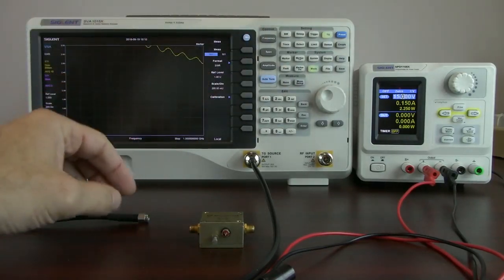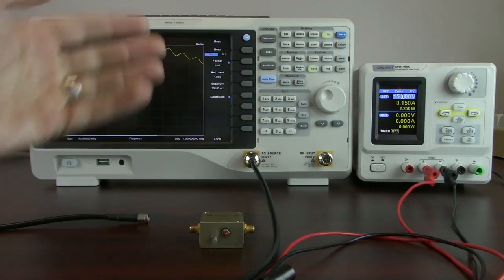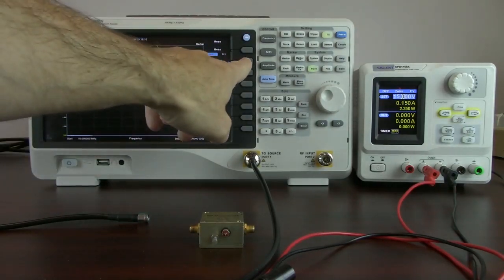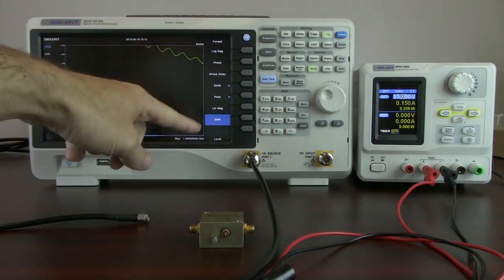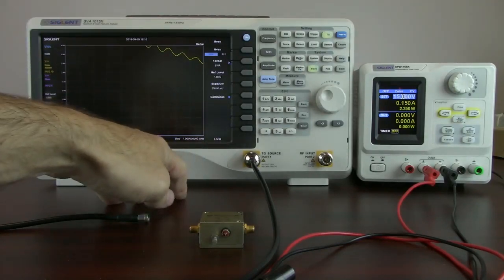And now we've got the ability to select S11 or S21. In this case since we're going to be looking at the VSWR we're going to look at S11. And for the format, we've got a number of different formats available. We're going to select SWR.